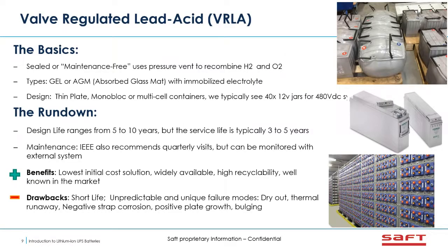The next main type of lead acid battery is the VRLA, or valve regulated lead acid battery. The basics here is it's a sealed, maintenance free design, where they use a pressure vent cap to recombine the hydrogen and oxygen gases into water to provide watering to the battery itself. There's two main types, gel or AGM, and this is how the battery electrolyte becomes immobilized inside of itself. And there's also a lot of different design types: thin plate, monoblock, multi-cell containers. And for UPS applications, we typically see 40 12-volt jars to make up the battery voltage for the UPS.